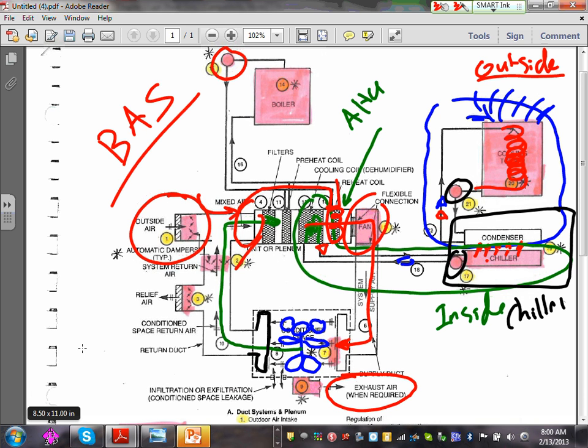There's also here, to maintain the pressure and not have a negative pressure in the room, they can exhaust the air out or they can bring air in. You have to balance between the air in and the air out, right? To maintain the pressure in the building like this. So here's an exhaust. Based on the building automation system, you can shoot too much air in the building, too much pressure, you can shoot it out, or you can bring air in to balance the pressure inside the building, or of course to get fresh air to your building. You don't have walls and all that stuff.